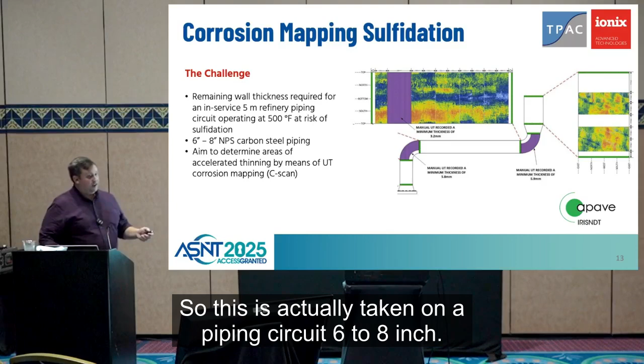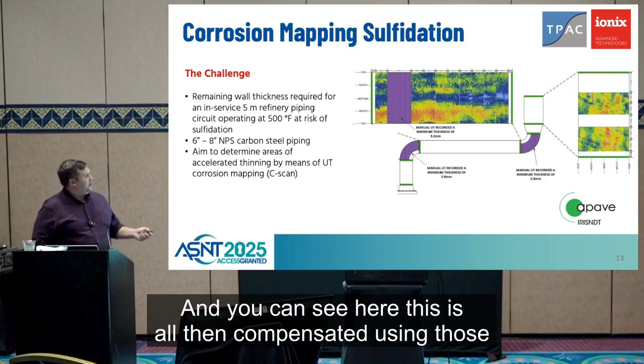So this is actually taken on a piping circuit, 6 to 8 inch. And you can see here, this is all then compensated using those curves beforehand to get accurate data, and it matches within plus or minus 0.002 inches of the ambient temperature measurement. So it's pretty good.